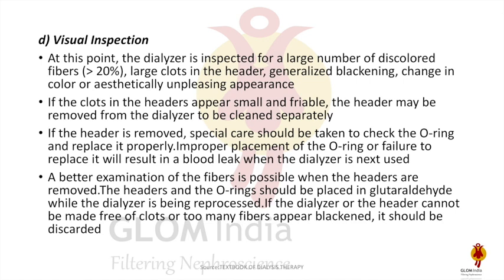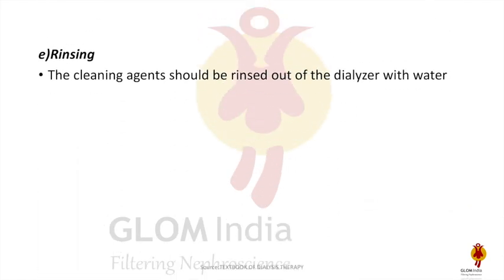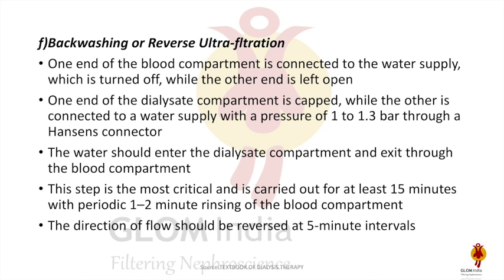If the dialyzer or header cannot be made free of clots, or too many fibers appear black, it should be discarded. For rinsing out the cleaning agent, backwashing and reverse ultrafiltration with water is used. One end of the blood compartment is connected to the water supply while the other end is left open. One end of the dialysate compartment is kept closed while the other is connected to the water supply at a pressure of 1 to 1.3 bar through a Hansens connector, so water enters the dialysate compartment and exits through the blood compartment.